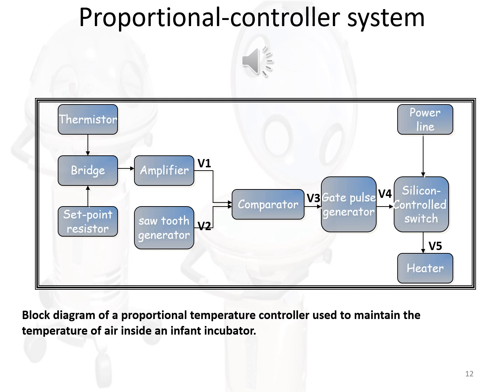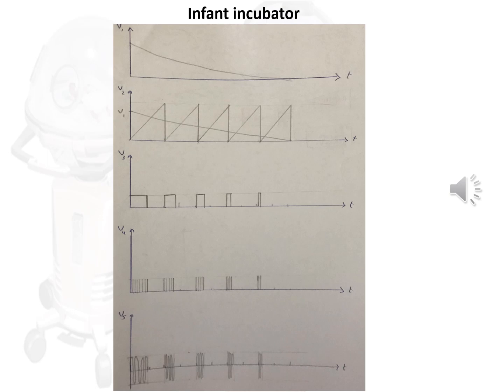When V1 is bigger than V2, the control switch is closed and power is applied to the heater. V1 is compared with V2 generated by the sawtooth generator. Maximum V1 should be smaller than maximum V2. When V1 is bigger than V2, the comparator outputs a signal V3. V3 excites a gate pulse generator that outputs a signal V4. V4 allows the closing of the silicon-controlled switch and the production of the signal V5, then power is applied to the heater.